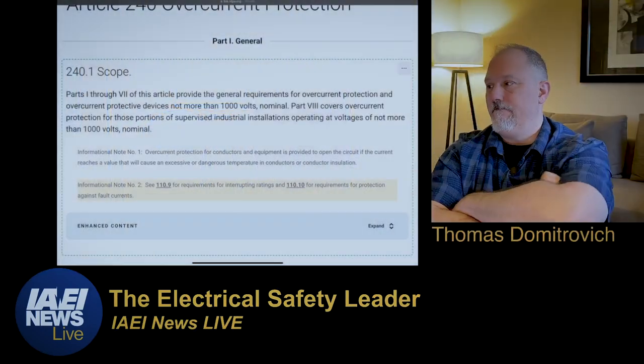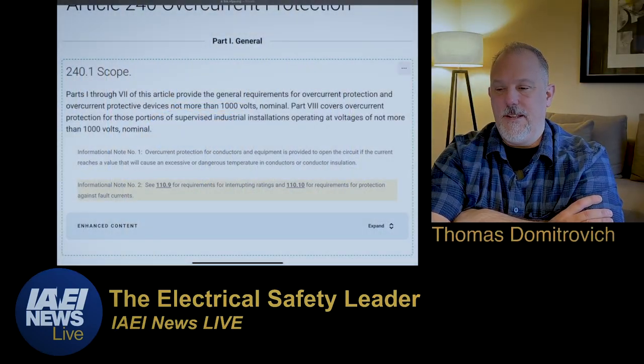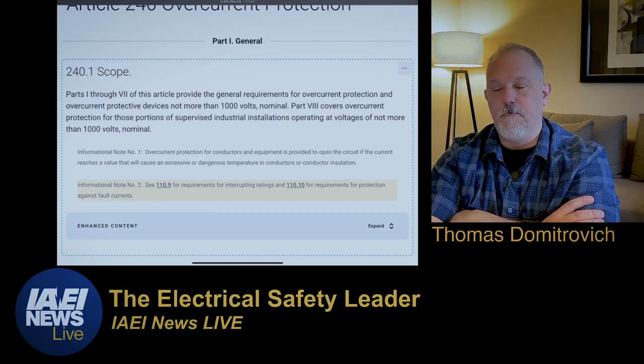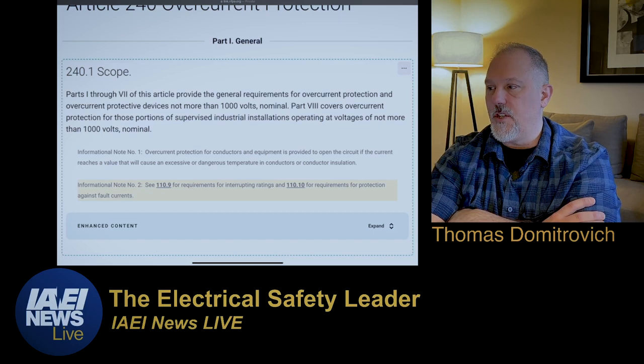Let's check 215. What we're going to learn about is consistency. Was panel 10 consistent? And we got it for 215. So in Article 215, we got that covered. We picked it up in 215, we picked it up in 225, we picked it up in 230. But in 240, yep, in 240, we just said 1,000 volts nominal. So I think we've got some work to do on the scope of Article 240.